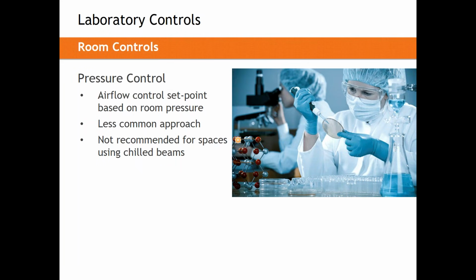Whenever you're using a high-speed control system, we don't recommend this pressure control. It is possible, the controls are always capable of it, but it is much, much harder to tune and much harder to maintain. The last thing I'll mention here before we open the floor up to questions and complete the presentation is if you'd like to do pressure control, there's 2 things you need to do. Number 1, you need to draw in pressure monitors. If you want to achieve pressure control, you need to measure room pressure. We have seen sequences that call out pressure control, but then specifically disallow room pressure monitors and sensors. There's a bit of an issue there in that if you want to control pressure, you do need to measure it.